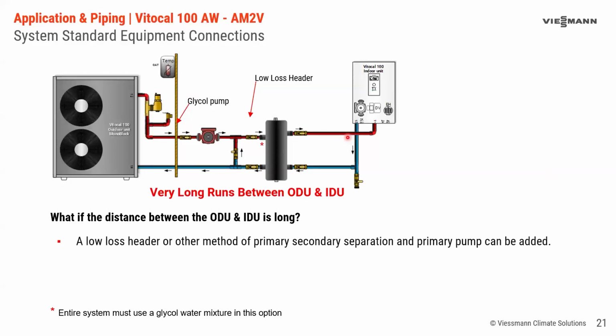So looking at this, we see this is very similar to what we did with the heat exchanger, except instead of a heat exchanger, we're going to use a low loss header or closely spaced tees or some other form of primary, secondary, right? A buffer tank or something like that. And again, we're going to put the bypass on this side just because we can eliminate any issues with this. But this system is all glycol, right? So remember, this is different than the heat exchanger where we had glycol on one side and just treated water on the other side. In this system, the entire system is full of glycol.